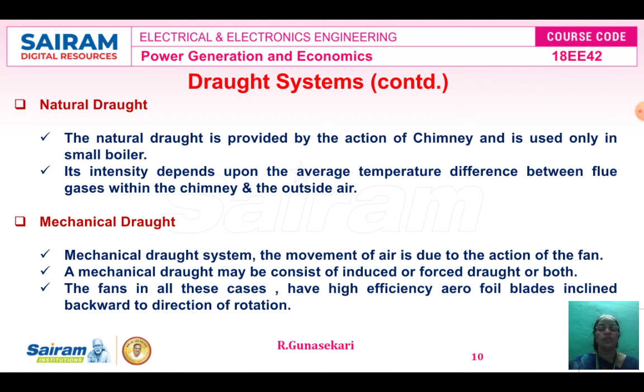In the induced draft system, the blower is installed near the base of the chimney and the burnt gases are sucked out of the boiler, reducing the pressure inside the boiler to less than the atmospheric one. This induces fresh air into the furnace. In the forced draft system, the blower is installed near the base of the boiler. This is the difference between the induced and forced draft system. Air pressure throughout the system is above the atmospheric pressure and air is forced to flow through the system.